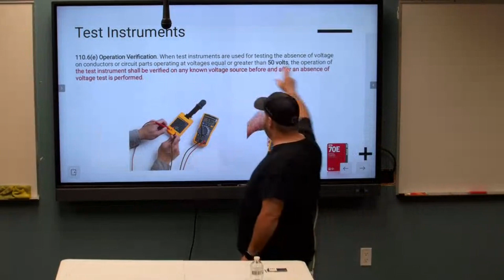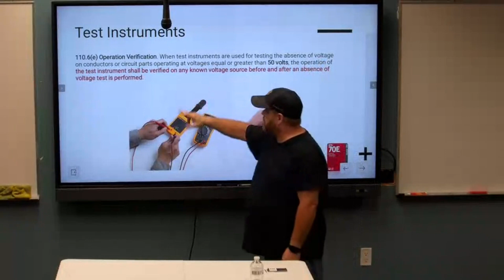And here's a real important one here. The 70E requires that when test instruments are used for testing for the absence of voltage on conductors or circuit parts operating at voltages equal to or greater than, here's the magic number again, 50 volts, the operation of that test instrument has to be verified on a known voltage source before and after the absence of voltage test is performed. So what are they saying? What they're saying is if we're going to be exposed to 50 volts or more, we have to do a pre-test on our test instruments.